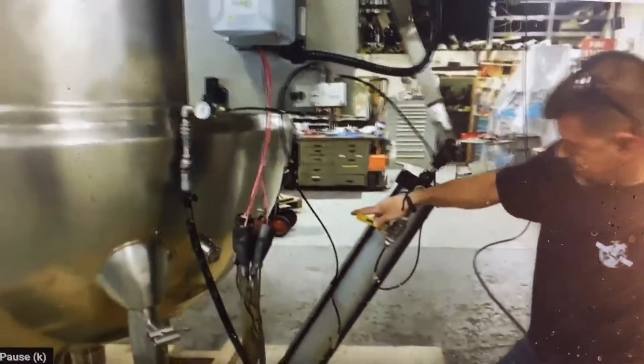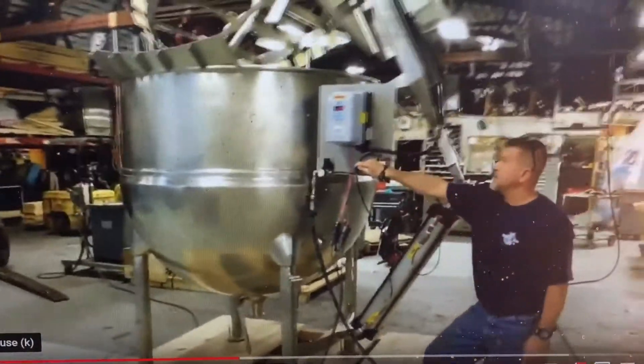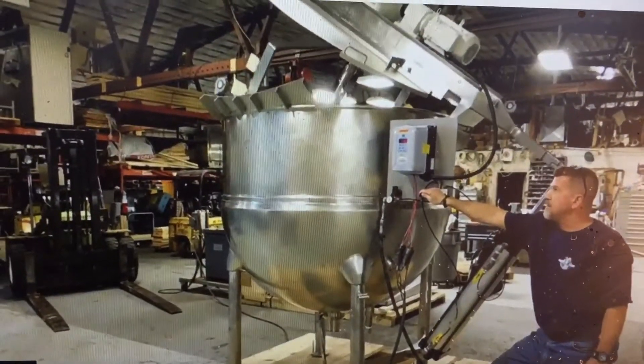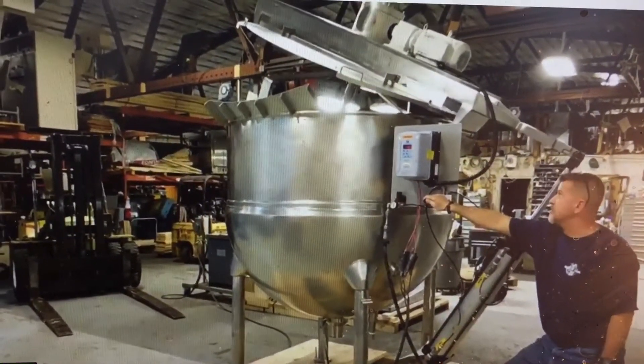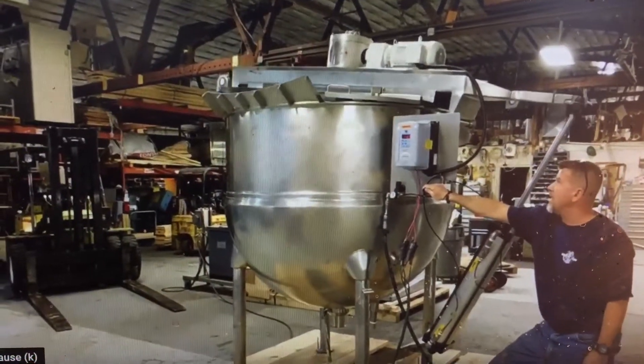Now, when you're ready to go down, open each valve again and you can just lower it down. I cannot stress enough — the scraper agitator must be at 90 degrees to the bridge, or the agitator will strike the opposing wall as it raises up.